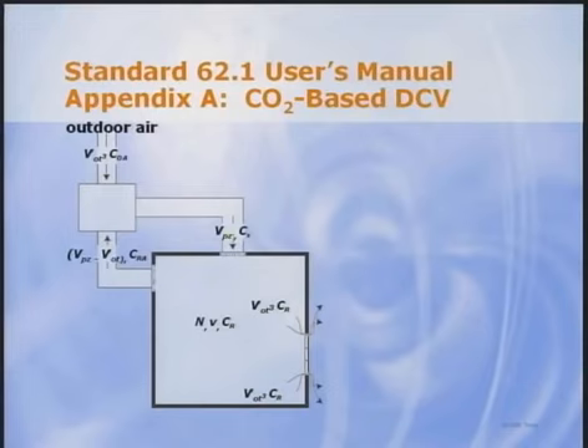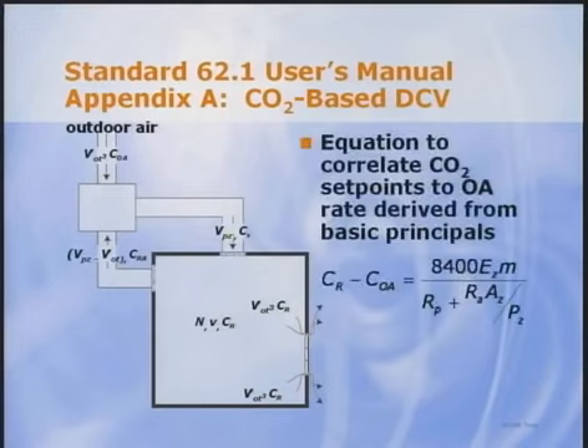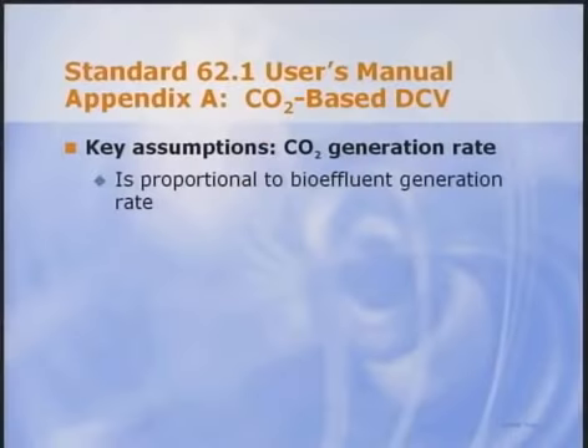Using basic principles, an equation is developed that correlates differential CO2 concentration, that's the difference between the indoor and outdoor concentrations, to the outdoor air ventilation rate. I'll discuss the equation in more detail later. The derivation of the CO2 ventilation rate equation includes two key assumptions. First, it assumes that CO2 is generated at a rate proportional to the rate that odorous bioeffluents are generated. These bioeffluents are what we are trying to dilute.